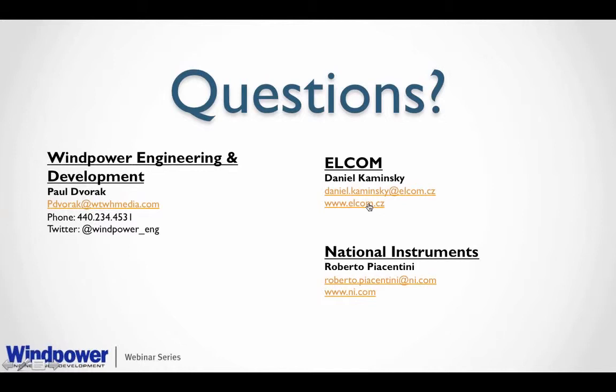I'm curious about where the sensor, the PMU, would actually sit in the grid - would that be on a telephone pole near the transformer, or back in the substation? Yes, I see. As shown in one of my slides with the basic architecture of the grid, typically the power quality analyzers or PMUs are installed at the substation where you transform the voltage from one level to another - for instance, from 400 kV to 110, or from 110 to 22 or 6 kV, or from that high voltage level, say 6 or 22 kV, down to 400 volts. Okay, thank you very much.